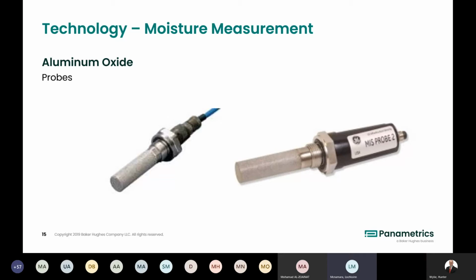Now, again, that would still be connected to a moisture analyzer, but you're able to use much longer cable runs with it. It also has the ability to store the calibration curve of the sensor directly on it, whereas with the analog sensor, you must enter the calibration curve into the analyzer. Each sensor has its own unique calibration curve. So when you're using it, you've got to make sure you have the correct cal curve associated with it. The one on the right, the MIS Probe 2, can also have a temperature and pressure sensor integrated into it. They would be contained under the sintered shield you see there.